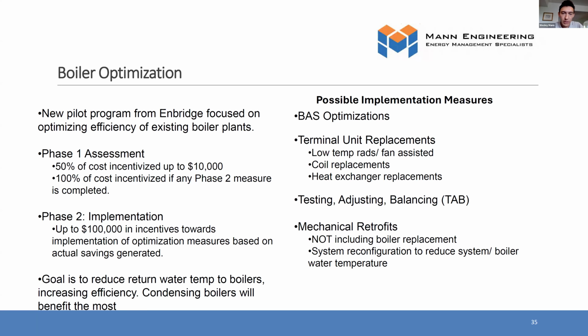Now, different measures we may recommend to do this is, one is just BAS optimizations. A lot can be done in software, outdoor reset curves, and just optimizing the water temperatures in the system to try and improve the efficiency. And another big thing is on heating systems. A lot of these buildings were designed to operate at 180-degree design temperature. So the RADs and all the terminal units, they may require very hot water, 180 degrees on design days, in order to actually provide enough heat. So one of the things we may look at is replacing RADs with low temp RADs, different heat exchanger or coil replacements on air handling units that are designed to operate at a lower temperature. And by doing that, that allows us to bring that heating curve down in the BAS and provide much greater boiler efficiency.